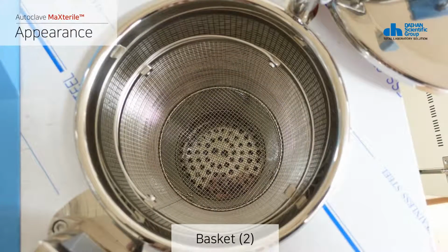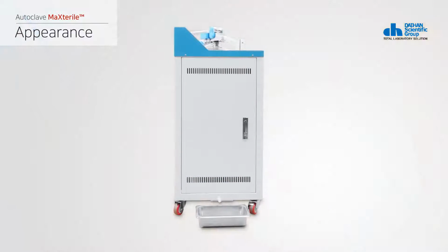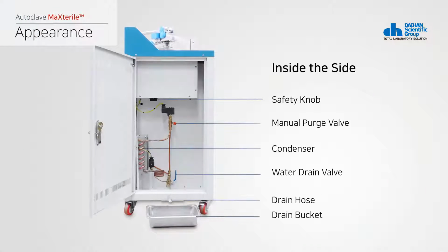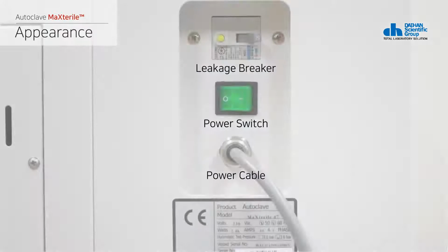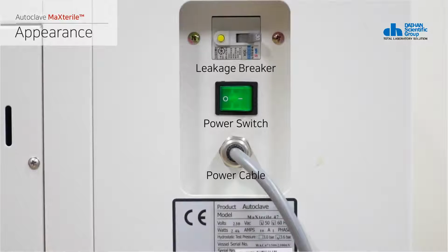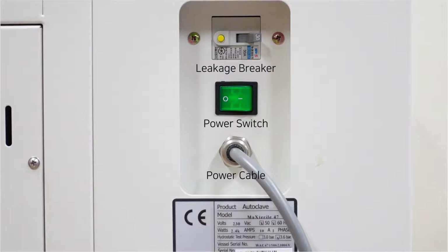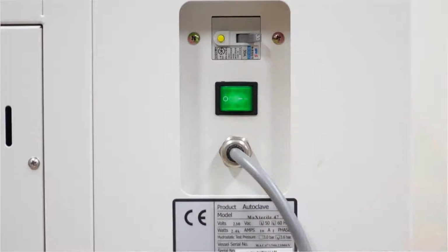When you open the power distribution box on the side of your product from above, you can find a safety knob that sets the temperature limit, manual push valve to emit steam by force in case of necessity, an exhaust steam condenser that helps the arrangement of steam after sterilization and provides a safe and clean sterilization environment, a drain valve for drainage and a drain hose for drainage and steam. The rear of the product consists of an earth leakage breaker, a power switch, and a cord line. Connect the cord before turning on the power switch.